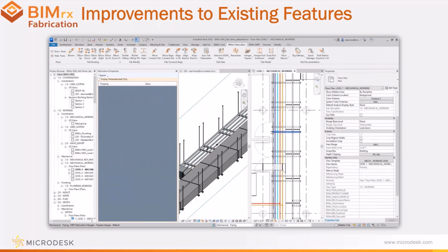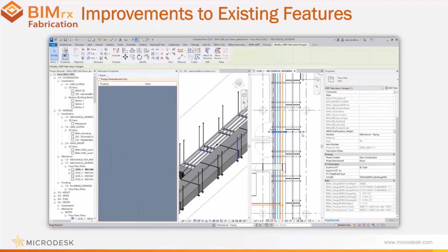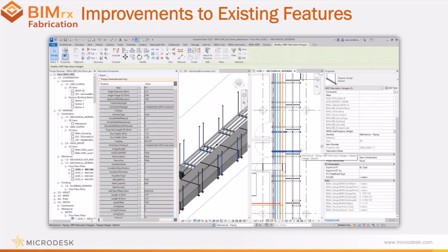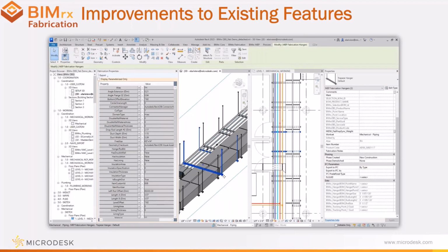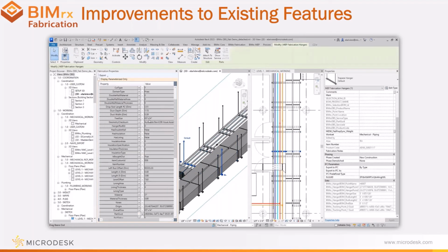It allows you to choose a host height element, then choose any other elements that we want to extend past. Clicking OK, we see that that expands out to host all of those. So once those hangers have been placed, we can also make some edits to the rods. New in 3.2, we have separated those rod lengths out, so we have individual control over each of them. These can be adjusted using the command and then easily flipped using the swap hanger command as well.